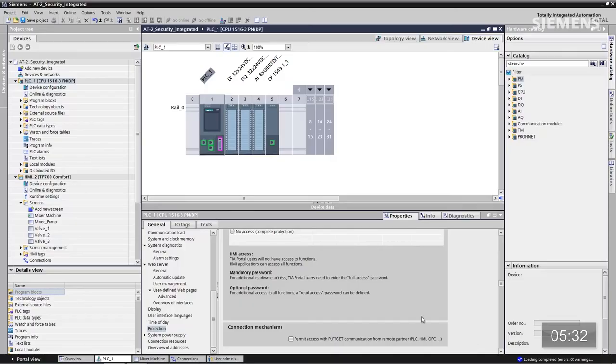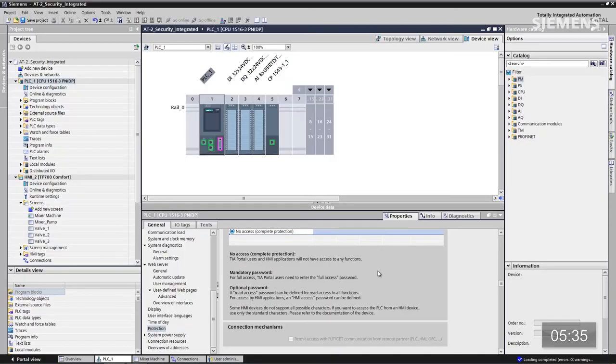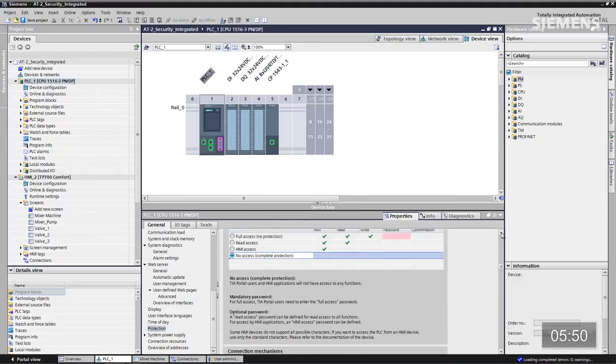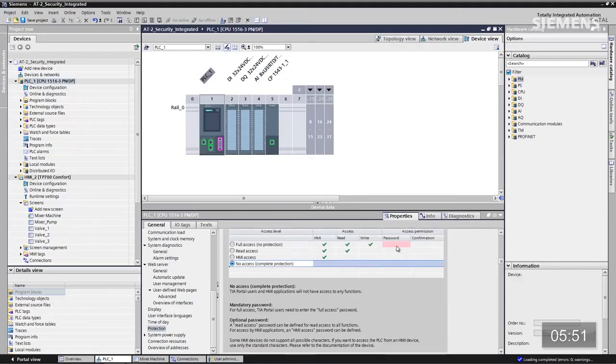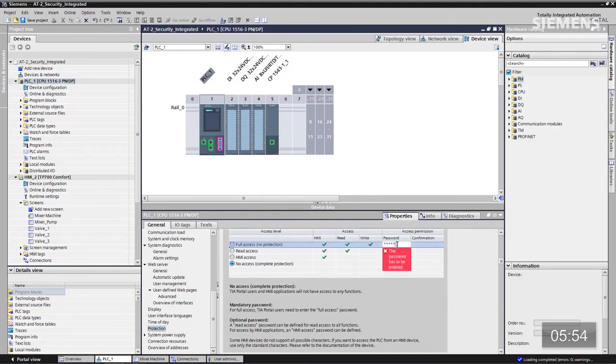Mais avec la protection de niveau 4, ces communications Get et Put depuis un OPC sont coupées. Les seuls moyens de communication seraient alors un T-Send, T-Receive de contrôleur à contrôleur, ou encore un E-Device sur le Profinet, qui se font tous deux par connexion sécurisée. Je souhaite un niveau 4 pour ce contrôleur. Je saisis ce mot de passe, c'est « Admin », il faut le taper deux fois.